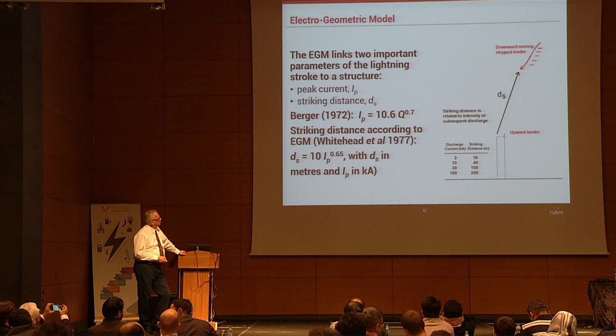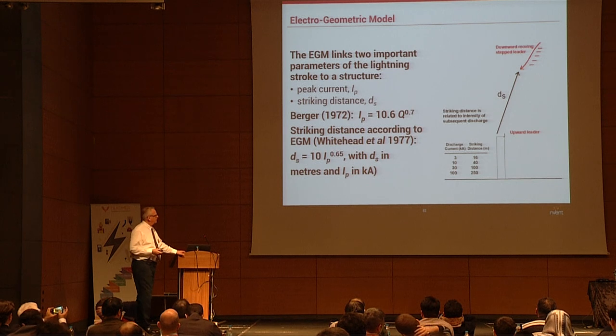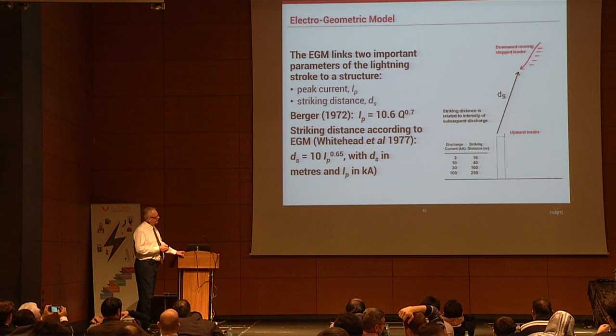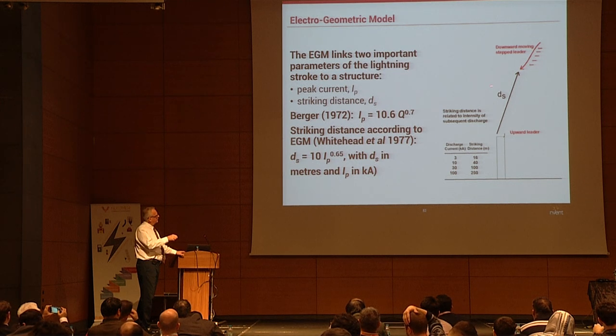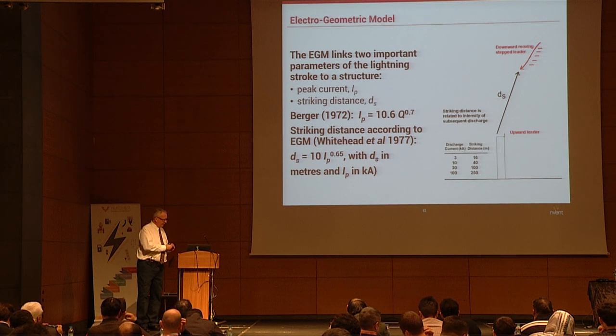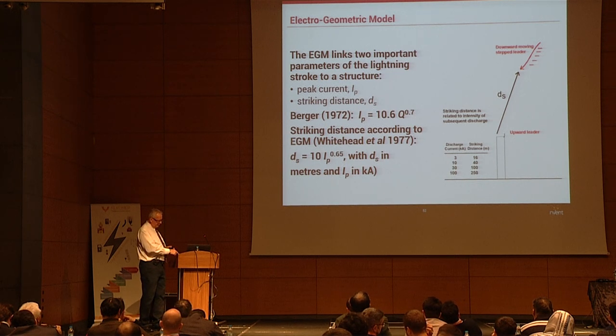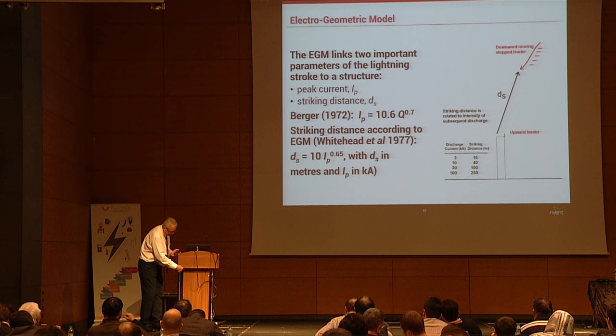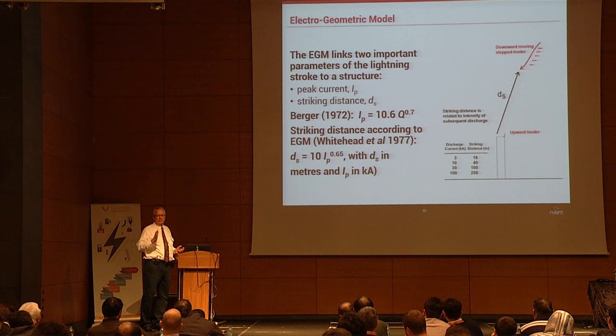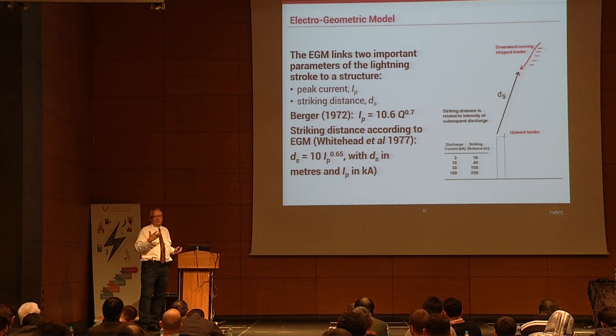These are some flaws of the electrogeometric rolling sphere model. It covers the important concept of striking distance, but the rolling sphere assumes the same statistical probability that lightning can strike anywhere on a building — corner, side, or top — which we know is really not true, although this is the most commonly used method worldwide.